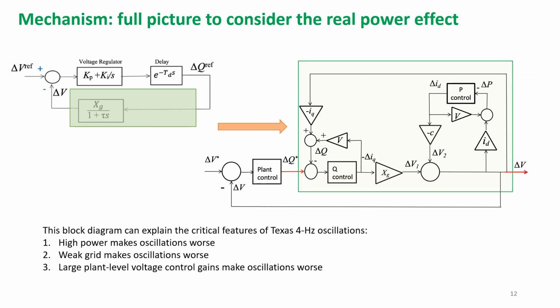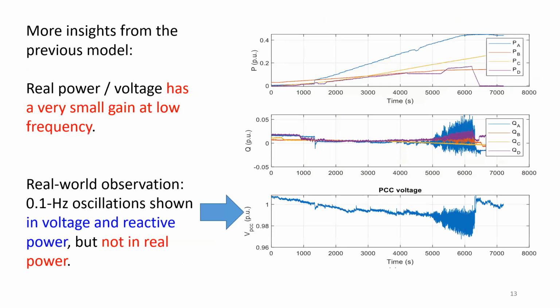So we said that's great, and we continued using this model because we found other oscillations. For example, there's another real world oscillation at 0.1 Hertz shown in the right figure—you can see it happens when power is ramping up. This is for a solar PV plant, about 1,000 megawatts total, and when it ramps up, oscillation happens in the voltage and reactive power, but not in real power.